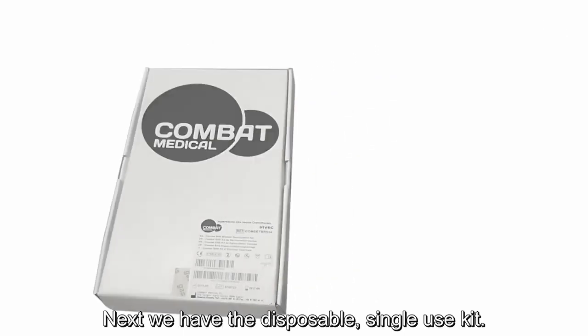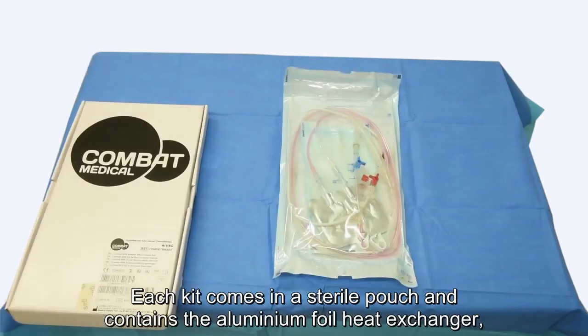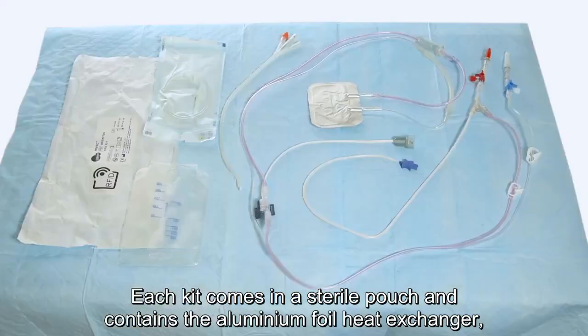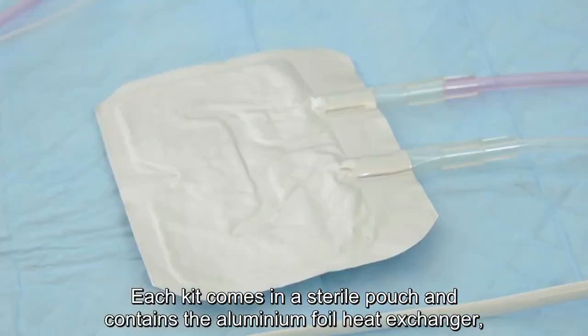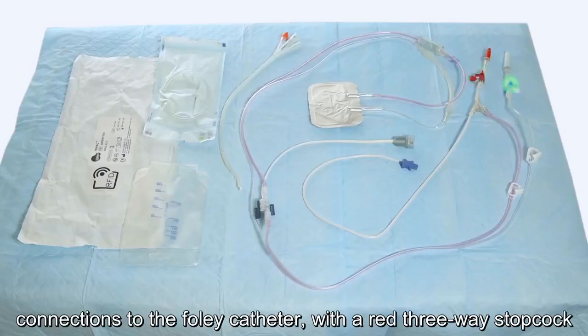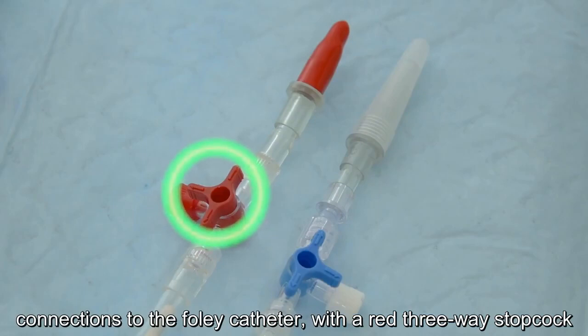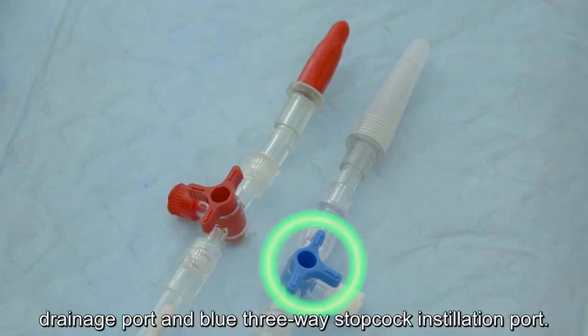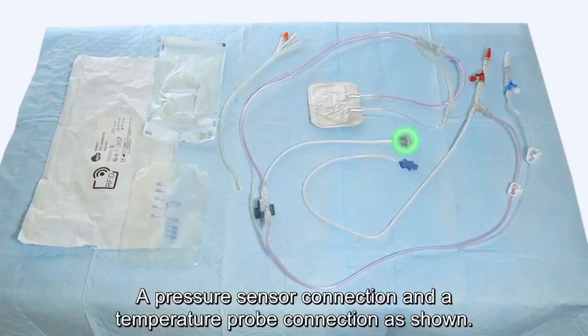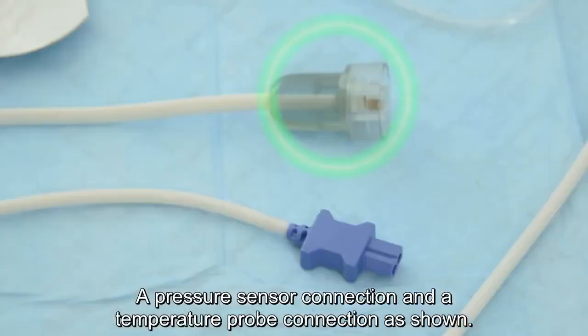Next we have the disposable single-use kit. Each kit comes in a sterile pouch and contains the aluminium foil heat exchanger, connections to the Foley catheter with a red 3-way stopcock drainage port and a blue 3-way stopcock instillation port, a pressure sensor connection and a temperature probe connection as shown.